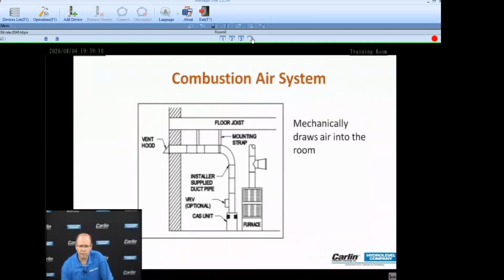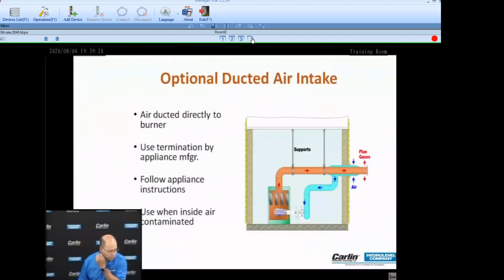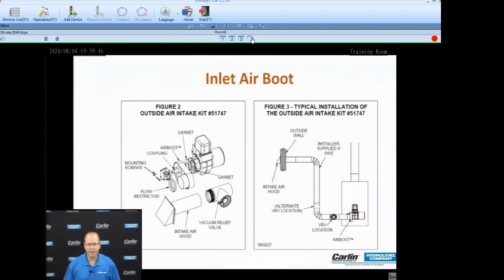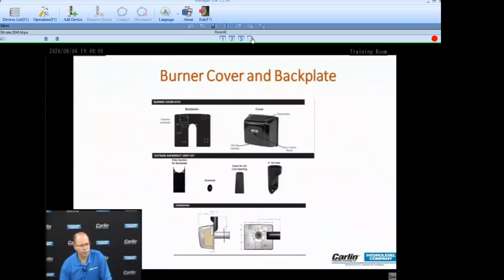You need to introduce combustion air mechanically. You could put some sort of a device. This one here looks very similar to a fan in a can, and you're introducing combustion air into the space where the appliance is located. Ducted outside air. This is a manufacturer's termination piece. So you've got outside air being ducted directly to the burner. This is an air intake kit that's adapted to the burner, and again, ducted to the outside to bring in combustion air.